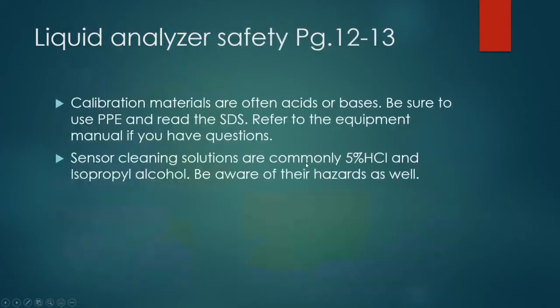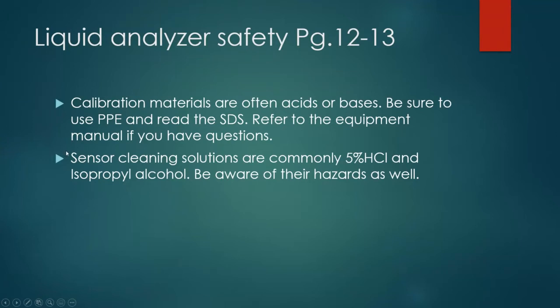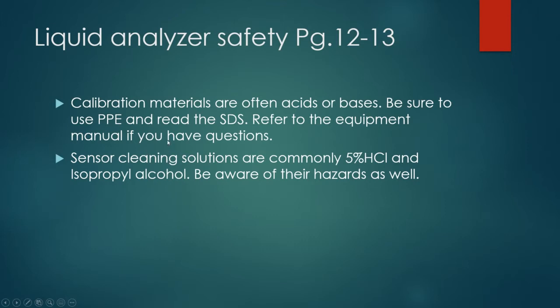More on safety: the calibration materials for liquid analyzers — particularly pH — often involve acids and bases, so again, use proper PPE and read the safety data sheets. Maintenance is basically limited to cleaning the sensor probes and sensor heads. Be aware that some sensor cleaning solutions can be hazardous — hydrochloric acid and isopropyl alcohol are commonly used, and either one in the face would cause a pretty rough experience, so safety is always important.